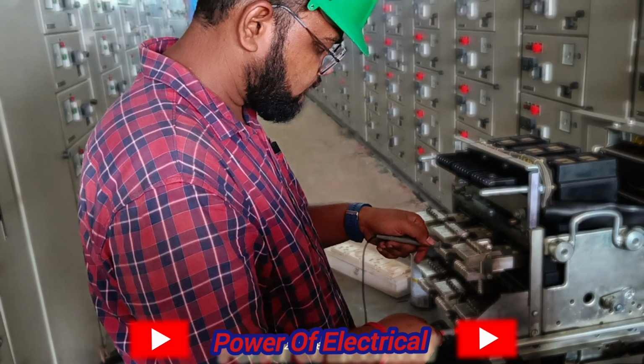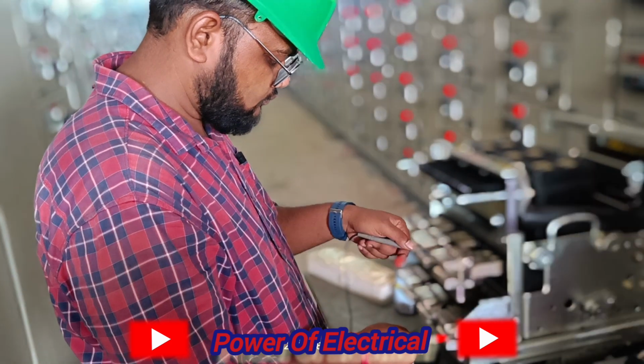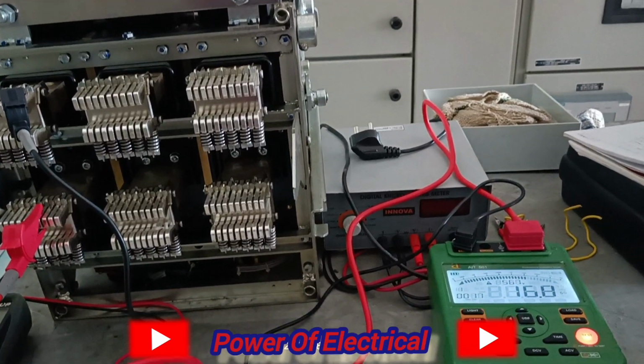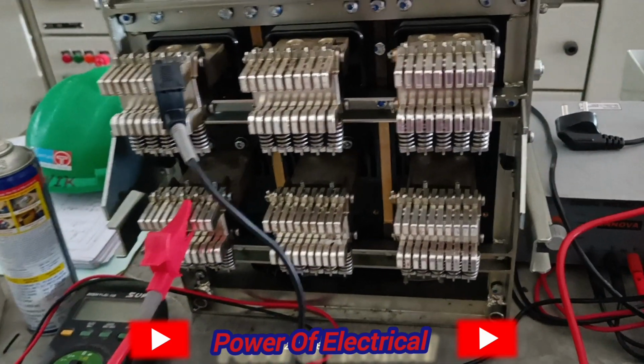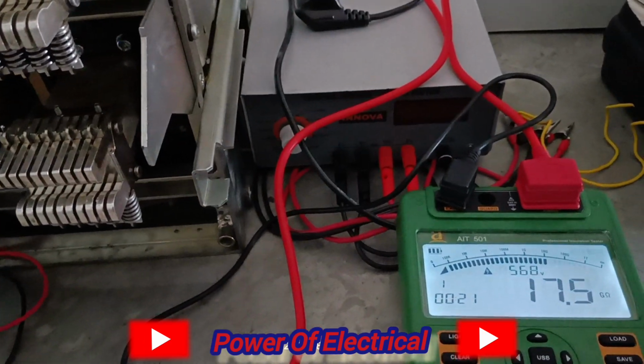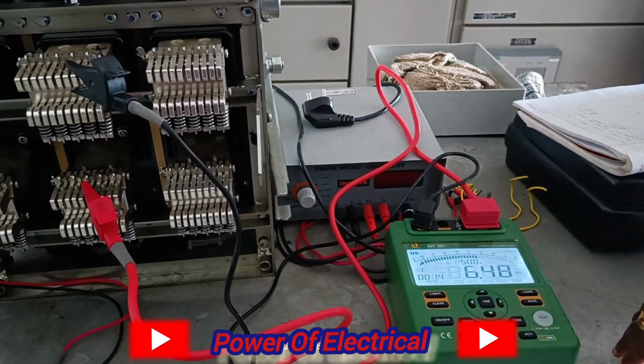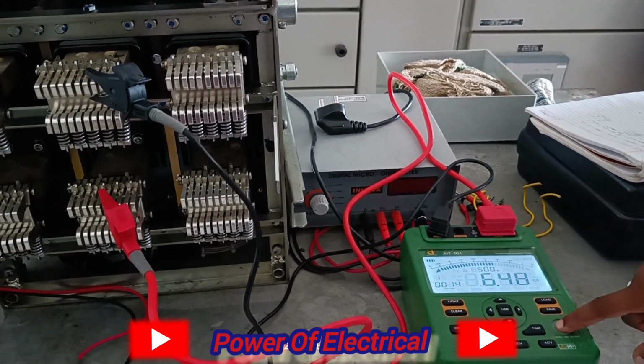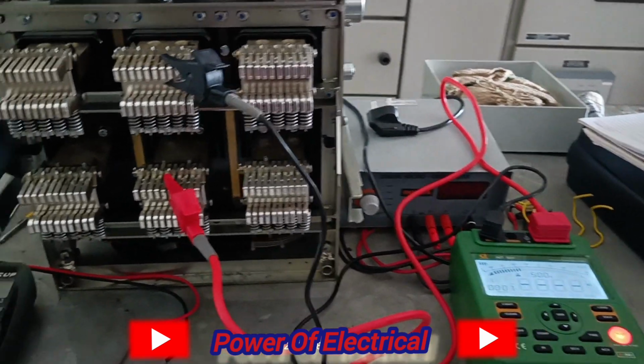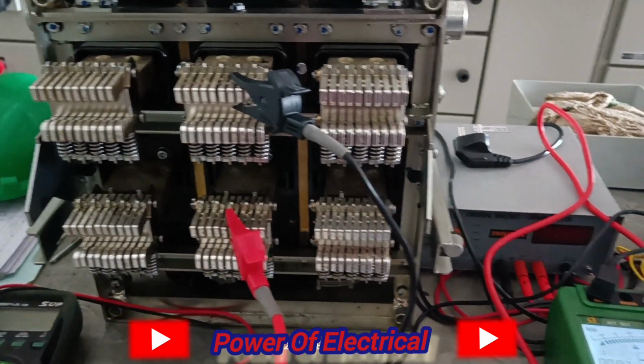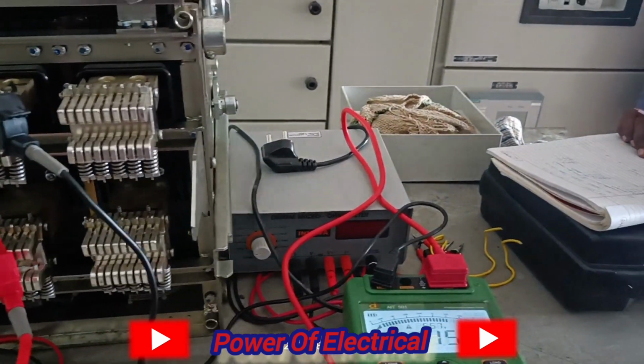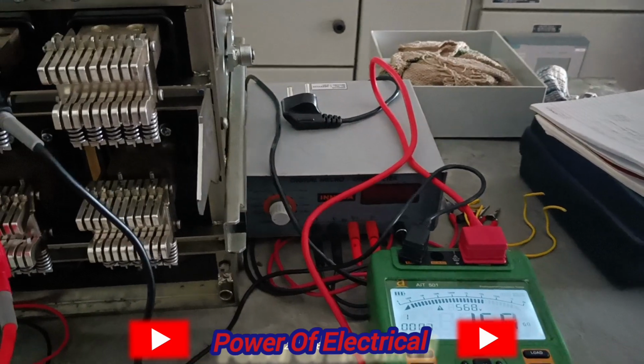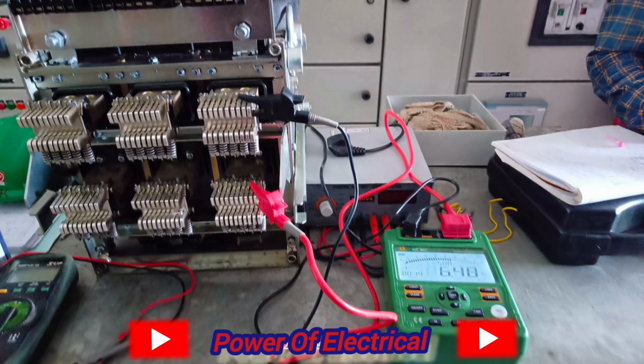Before IR testing, we need to confirm that our circuit breaker is off or on. So we need to check the pole to pole continuity to confirm the circuit breaker is off. After confirming the circuit breaker is properly off, we connect the meter probe to the pole and inject 500 volt for LT system and get the value. For the pole to pole, we get a value greater than 5 gigaohm.